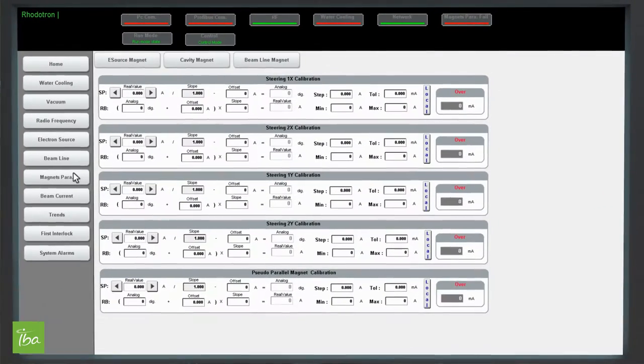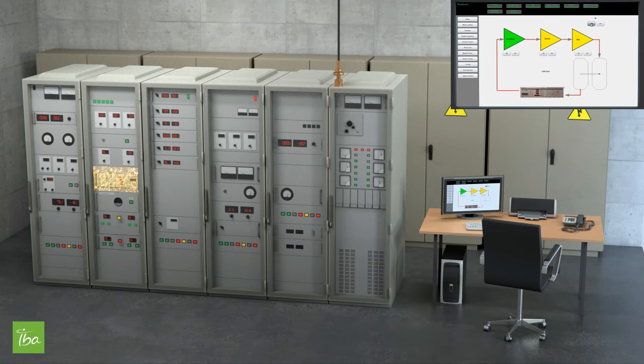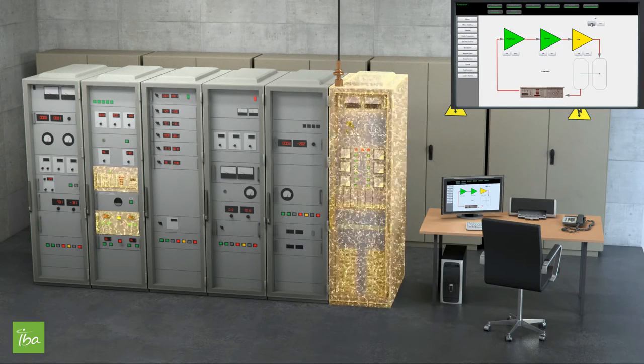As you can see, the activation of the radio frequency system happens in four different stages. A small signal is generated by the low-level RF rack. The signal is amplified by the pre-driver, then amplified a second time by the driver amplifier.